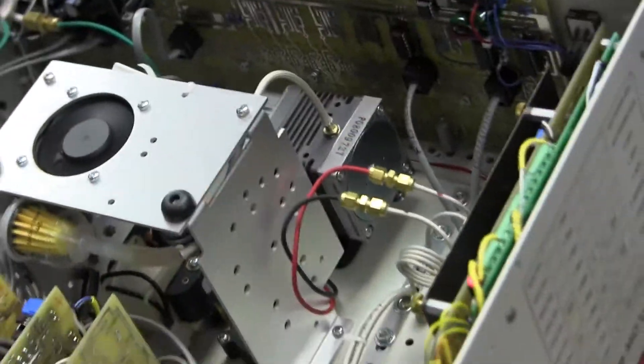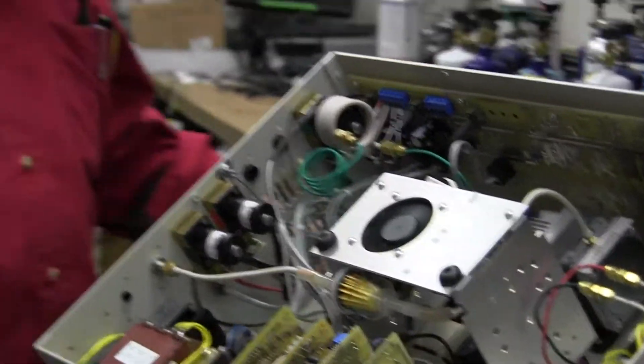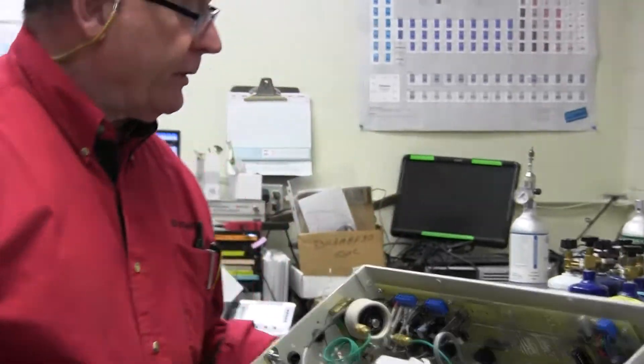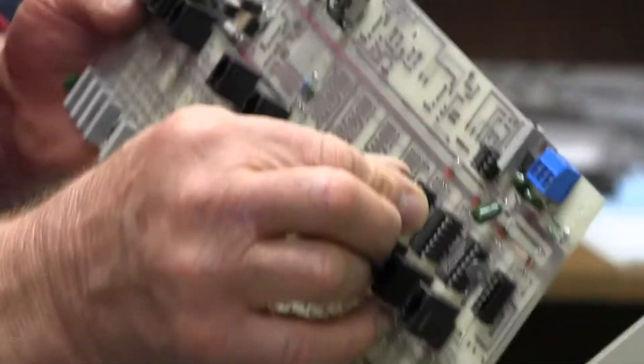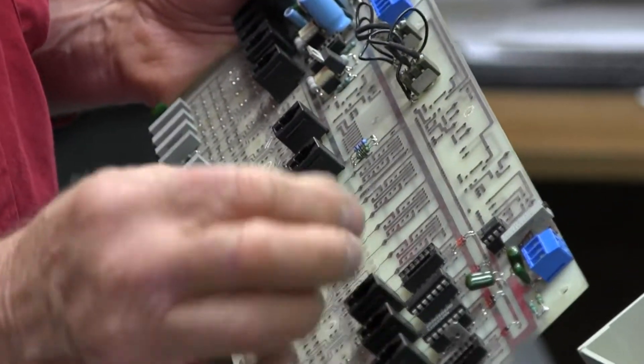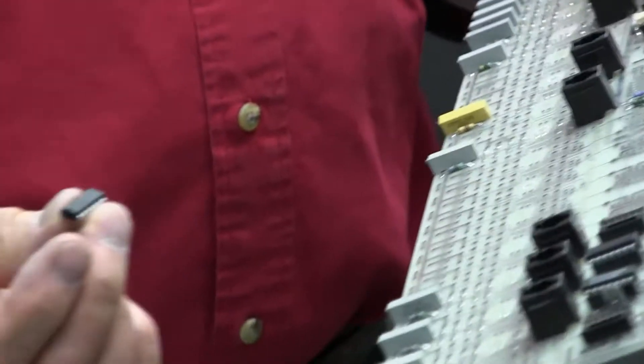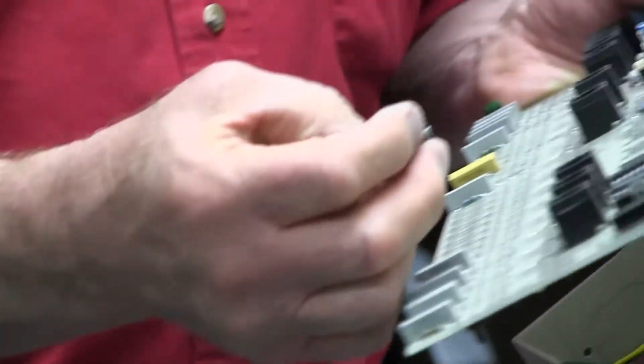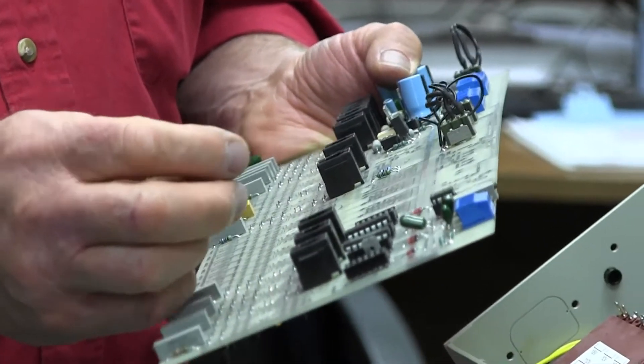But there's something that can happen occasionally, and that's that one of the chips that does the supervising to make sure that the thermocouple temperature is reading somewhere between 5 and 425. This is one of those supervisory chips. It's called an LM324 chip, sometimes an LM224 chip. We use both. They're interchangeable, almost identical.